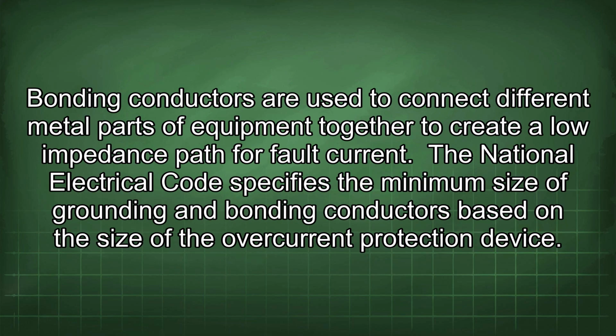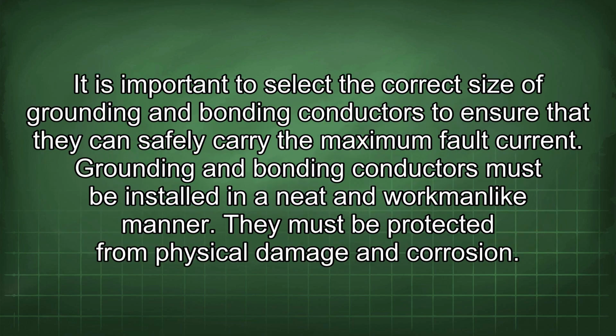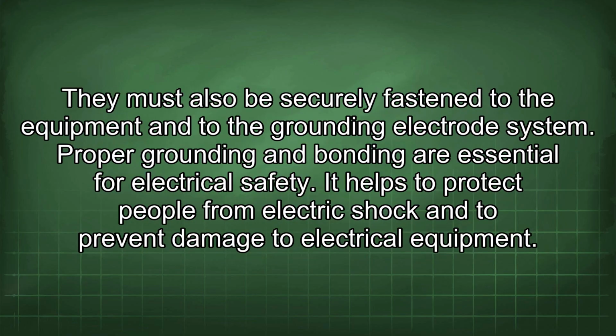Bonding conductors are used to connect different metal parts of equipment together to create a low impedance path for fault current. The National Electrical Code specifies the minimum size of grounding and bonding conductors based on the size of the overcurrent protection device. It is important to select the correct size of grounding and bonding conductors to ensure that they can safely carry the maximum fault current. Grounding and bonding conductors must be installed in a neat and workmanlike manner. They must be protected from physical damage and corrosion. They must also be securely fastened to the equipment and to the grounding electrode system.